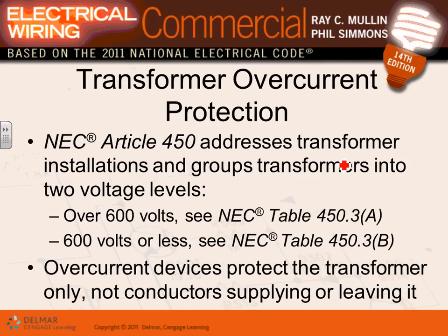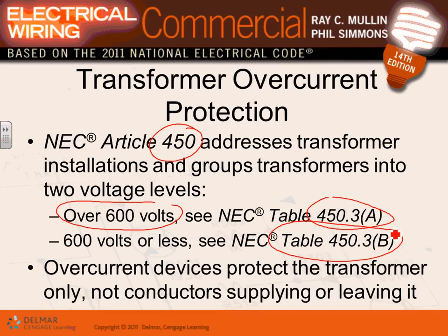Okay, transformers, guys. The article that talks about transformers is Article 450. The single most important thing about transformers is being able to protect them from short circuit using fuses and circuit breakers. They have two tables that can be used, and soon to change. One table covers over 600 volt. The first one, if either the primary or the secondary is over 600 volt, you use this table. The second table, 450.3(B), applies if the primary and, I can't emphasize the word and enough, and the secondary are 600 volt or less.